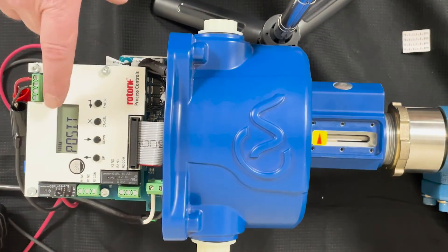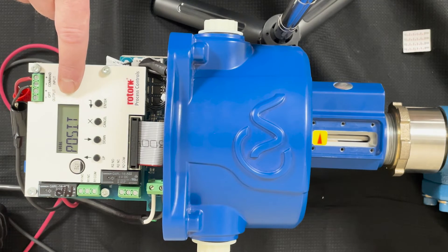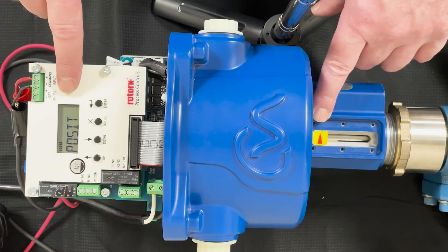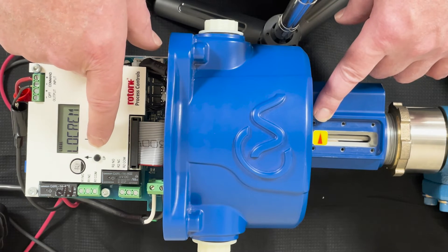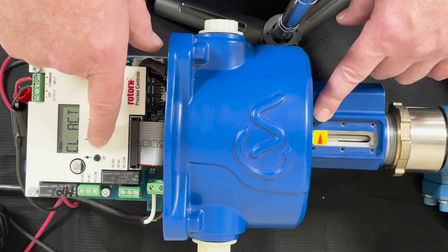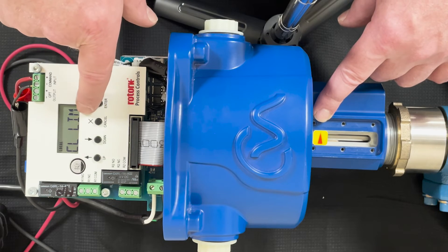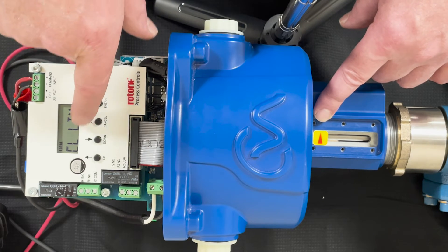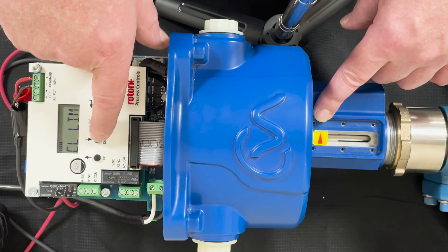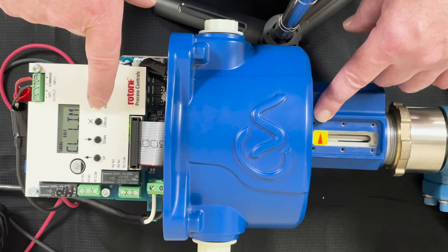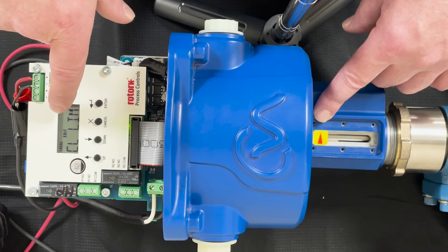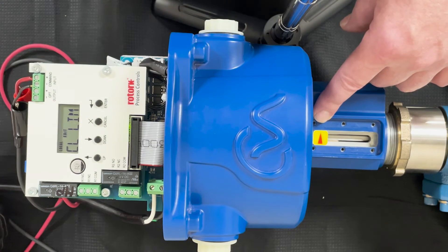Now we have to set the positioner to the zero limit. In order to do that, we want to go to the CL limit. Hit enter and enter again and it says edit. Now we can set our 4 milliamps on the analog, and then we hit enter again and now it's saved.